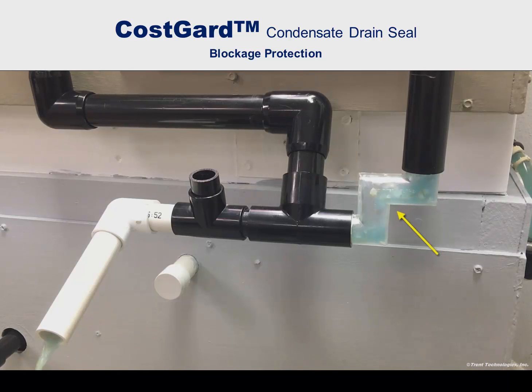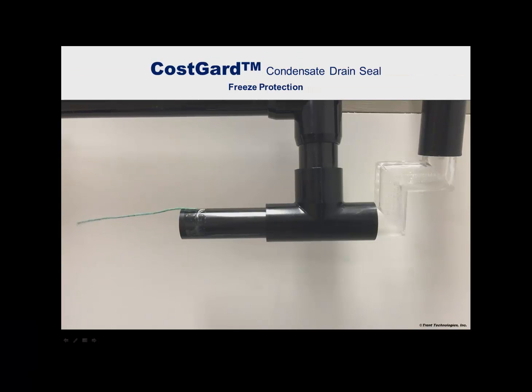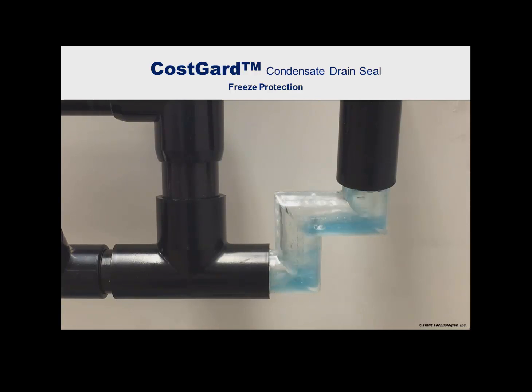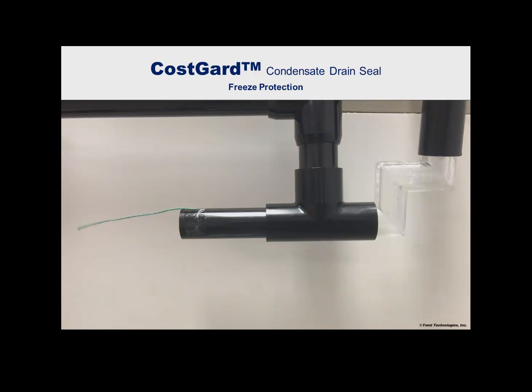Note the churning action produced by the air entering the device and the rapid passage of the debris. Unlike the condensate trap, the CostGard condensate drain seal retains no condensate and is unaffected by freezing temperatures that destroy traps. During the cooling operation, when condensate is being generated, it flows rapidly through the drain seal, including the mitered elbows. Once condensate flow ceases, the warmer air that forms the drain seal quickly evaporates any water that may be held inside by surface tension.